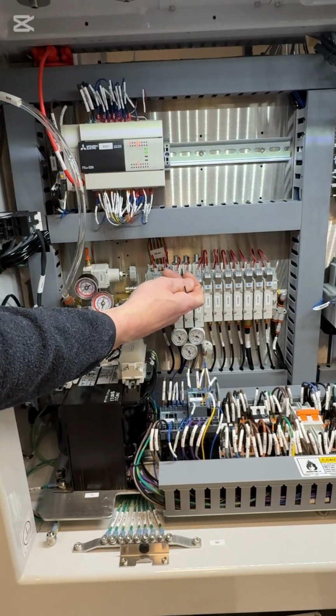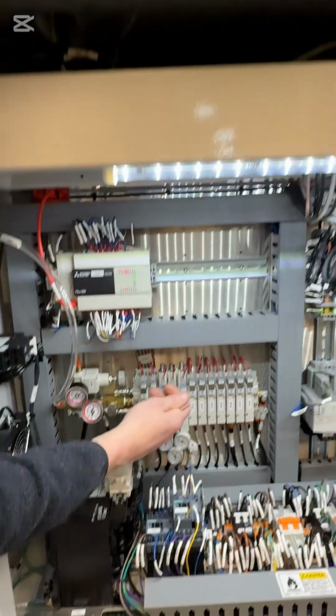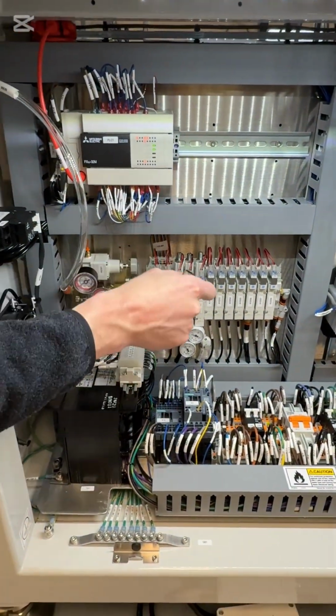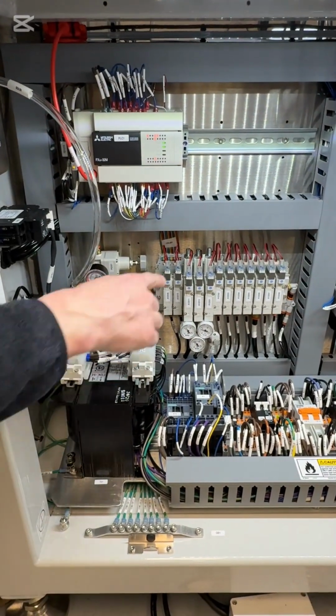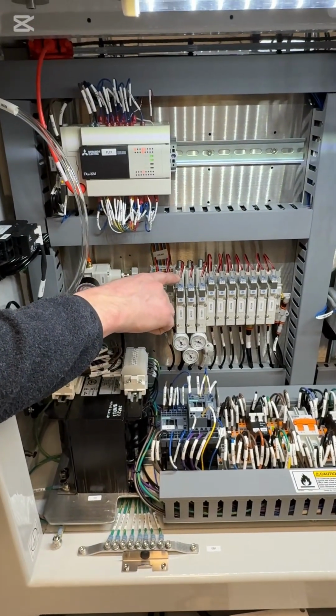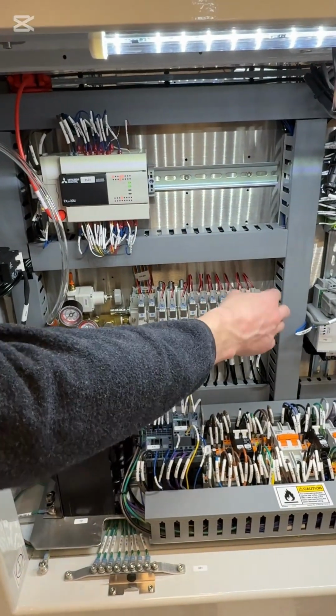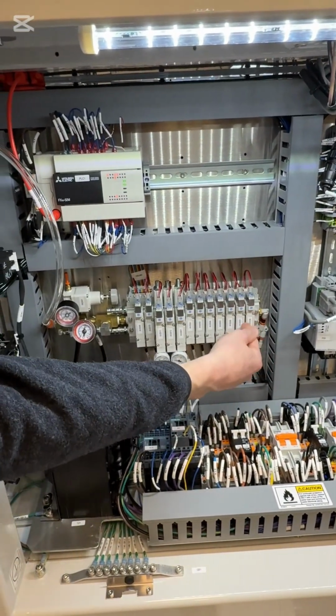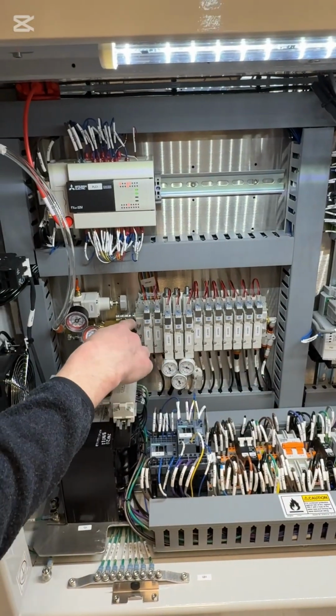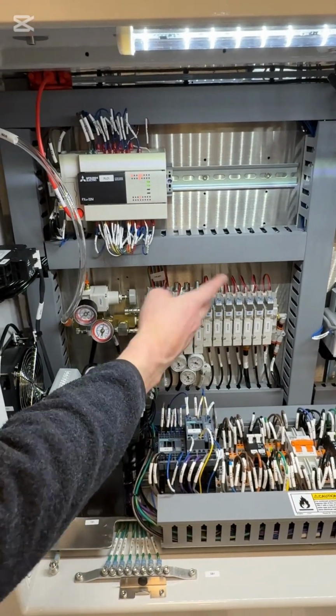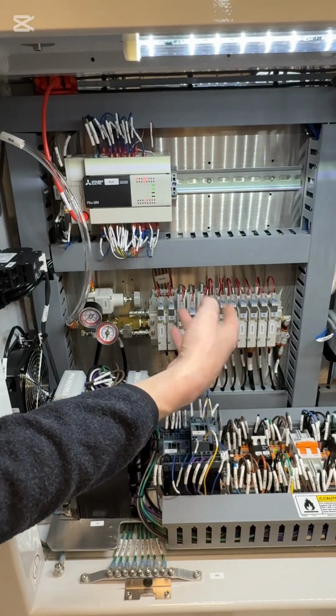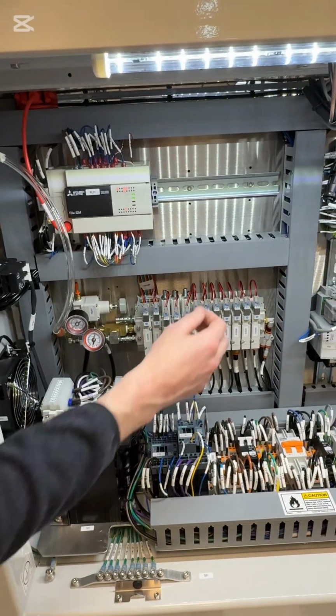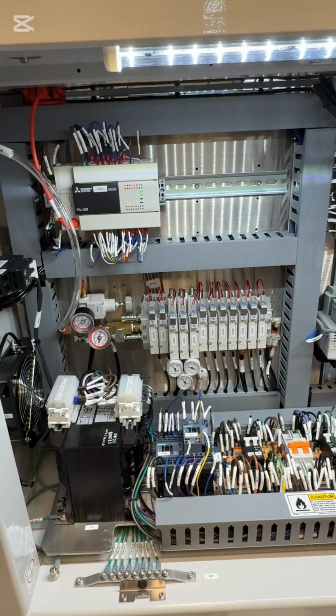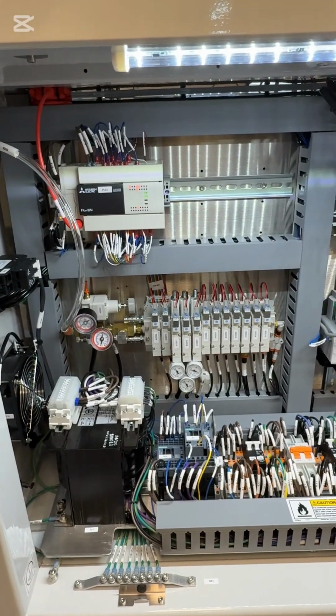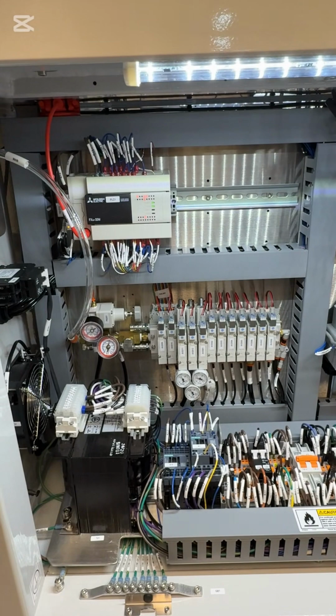It could be the cable going into the solenoid of the air valve. So it's good to check these cables, make sure they're seated correctly. Another way you can make sure that it's the cable that is the problem, or if it's not the problem, you can take, say, AV2008 or AV2009, and just swap these cables around. And if the problem resolves after swapping the cable, then it's the cable. Yes, you can check by swapping the two cables and seeing what switches on and what switches off.